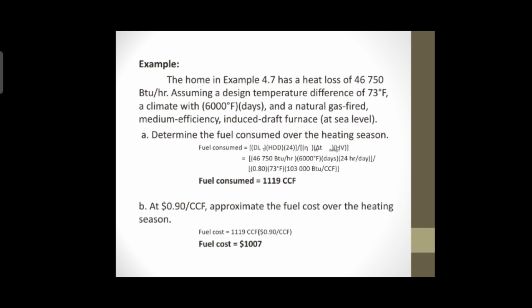So, here's the example. The home in example 4.7 has a heat loss of 46,750 BTU per hour. Assuming a design temperature difference of 73 degree Fahrenheit, a climate with 6,000 degree Fahrenheit-days, and a natural gas-fired medium efficiency induced draft furnace at sea level. So letter A, determine the fuel consumed over the heating season. Fuel consumed is equals to DL times HDD times 24 all over eta sub HS, delta T design times HV. So we're gonna be having here an answer of 1,119 CCF.